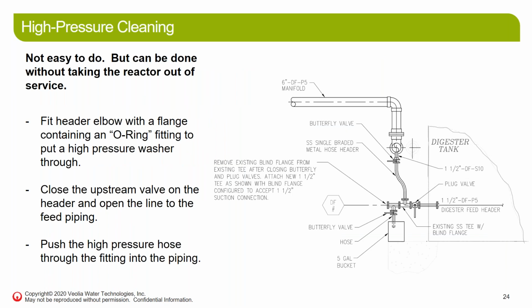High pressure cleaning: this is an example of a procedure we developed for how to do it. It's not really easy, but technically you can do it with the system still in service. You don't have to take it fully down. You could also do this with the system out of service. That would be preferred because it's easier and you don't have to worry about the tank full of water. But essentially you take those feed headers, and if you connect a T on the end, you can hook that T up to a bucket or a drain somewhere. And on the blind end of that flange, you can put a high pressure washer with some kind of O-ring seal and essentially extend a pressure washer in through that header while draining it down, flushing that system out with the high pressure through the header and draining it back down into the bucket or drain.